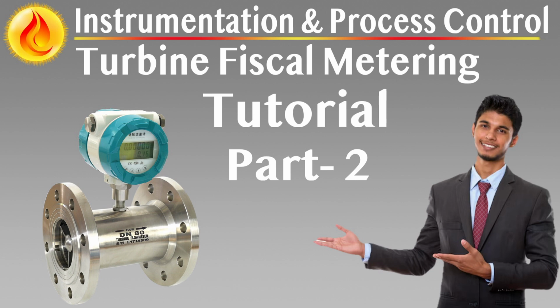Stream failures are handled by deactivating the faulted run and enabling a standby. In the event of stream computer failure, the affected microcomputer must be hot swappable using plug-in spare units. This approach ensures rapid recovery and avoids production interruption. Each microcomputer is required to preserve essential data during swaps, including meter totals and configuration parameters, digital protocols, and data integrity. To eliminate conversion errors and maintain signal fidelity, digital communication protocols such as HART or Foundation Fieldbus are preferred for transmitter to microcomputer links. These protocols support high-resolution signal transmission, device diagnostics, and live status reporting.